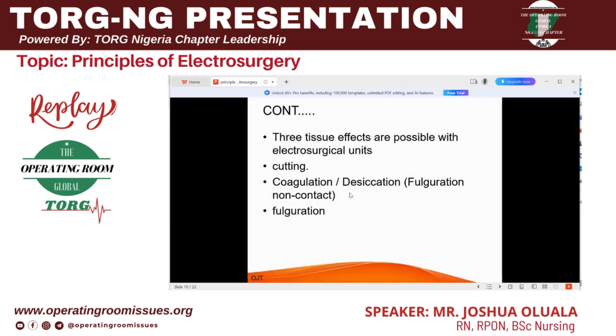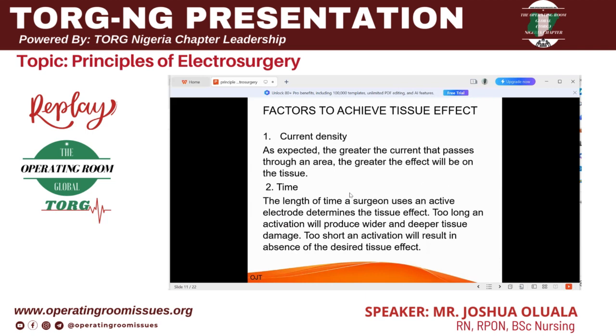Now, this tissue effect we are talking about can be in the form of cutting, can be in the form of coagulation or desiccation, and can be in the form of fulguration also. So we want to look now at the factors to achieve tissue effect. There are 5 different factors to achieve this tissue effect. In all we do in the theater, we use the diathermy, but the process must go through these 5 factors to achieve the desired effect. Number one of them is the current density. As expected, the greater the current that passes through an area, the greater the effect. This is very straightforward.